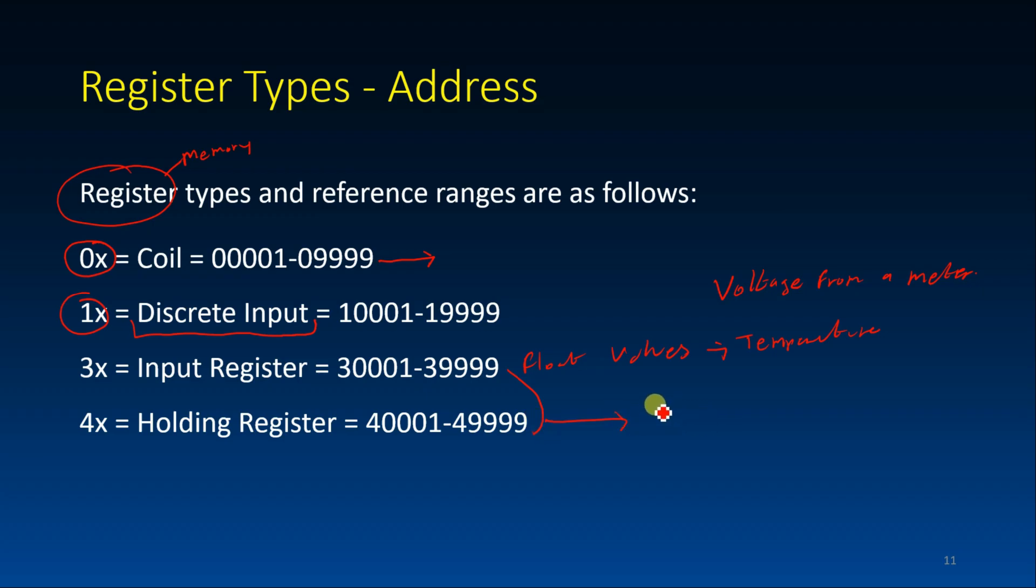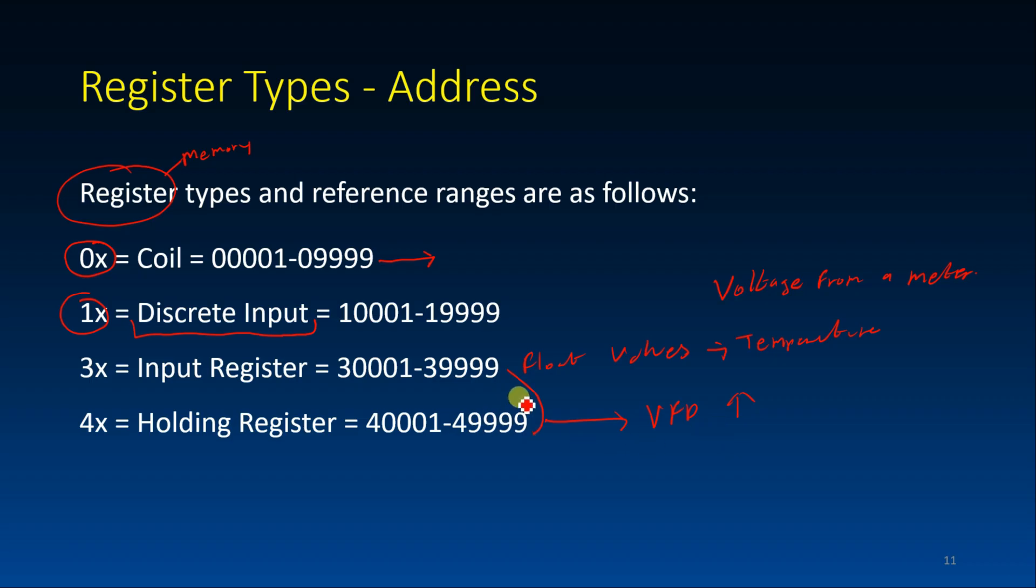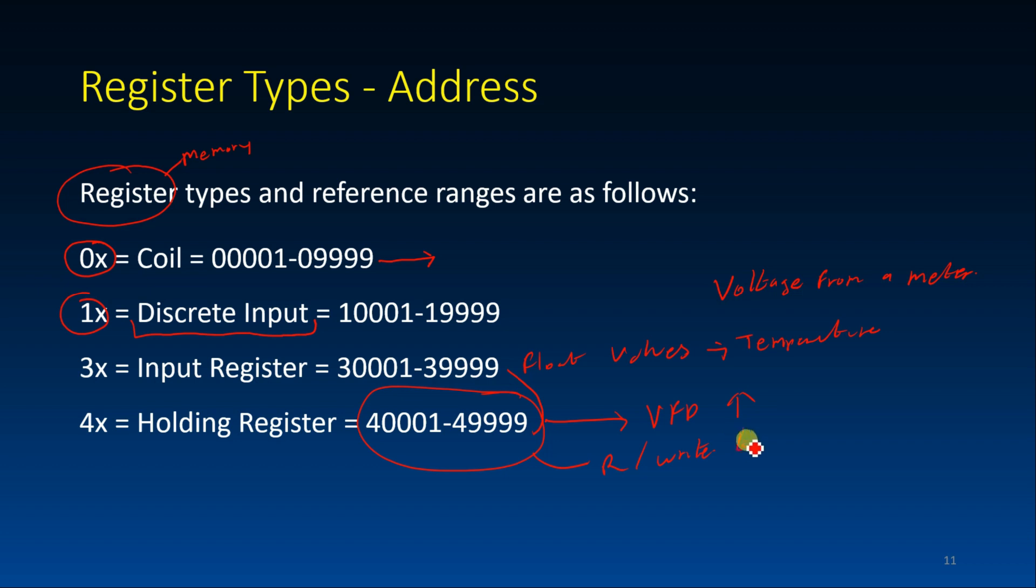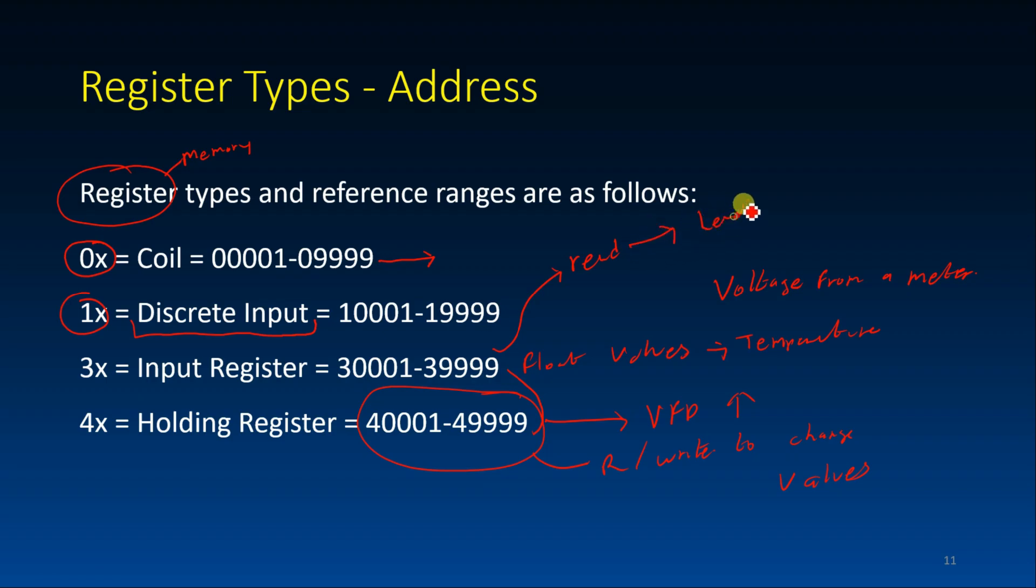And here, this one is used, let's say we have a VFD. We want to increase the speed. So we must write a value to the VFD. So these registers we can read and write to change values. But whereas this one we can only read. Read is for example a level sensor. So we only read because it will just give a value of the process.